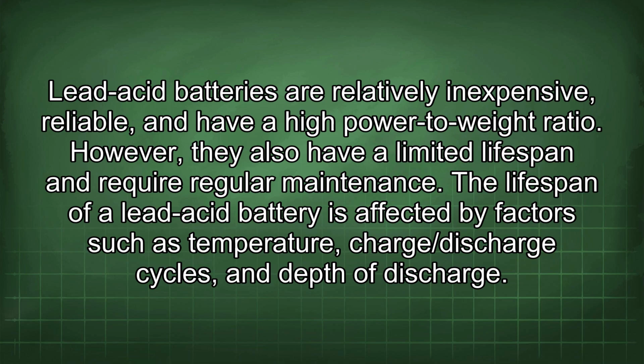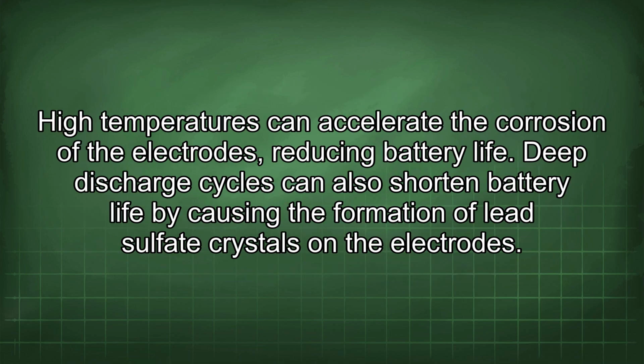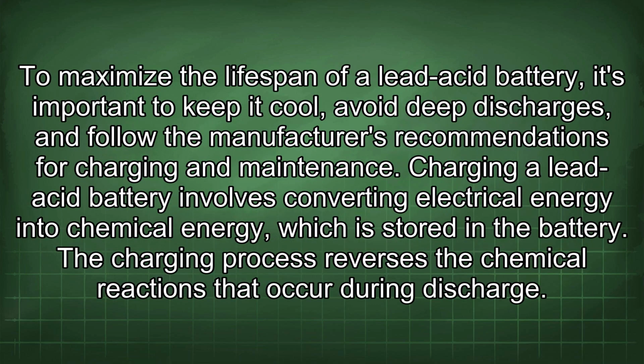The lifespan of a lead-acid battery is affected by factors such as temperature, charge/discharge cycles, and depth of discharge. High temperatures can accelerate the corrosion of the electrodes, reducing battery life. Deep discharge cycles can also shorten battery life by causing the formation of lead sulfate crystals in the electrodes. To maximize the lifespan of a lead-acid battery, it's important to keep it cool, avoid deep discharges, and follow the manufacturer's recommendations for charging and maintenance.